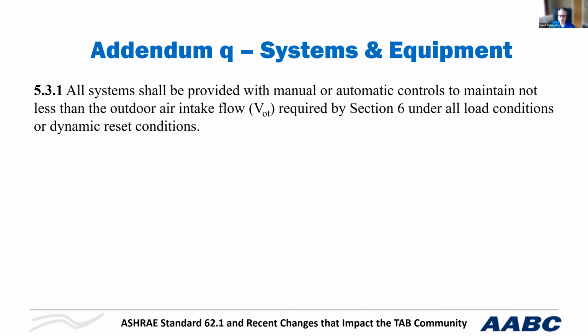And this is making conflicting control. So for example, if the temperature is coming close to the set point in the space and the requirement is that the fan speed turn down, and all of a sudden people start leaving the space, the damper wants to start opening because the fan speed is turning down, but now people are leaving the space, so the damper wants to start resetting back because there's less people in the space and you need to ventilate for fewer people. So that's the challenge that we have.